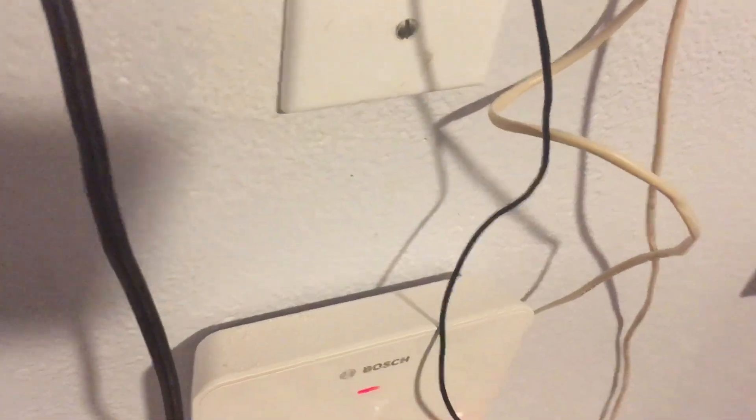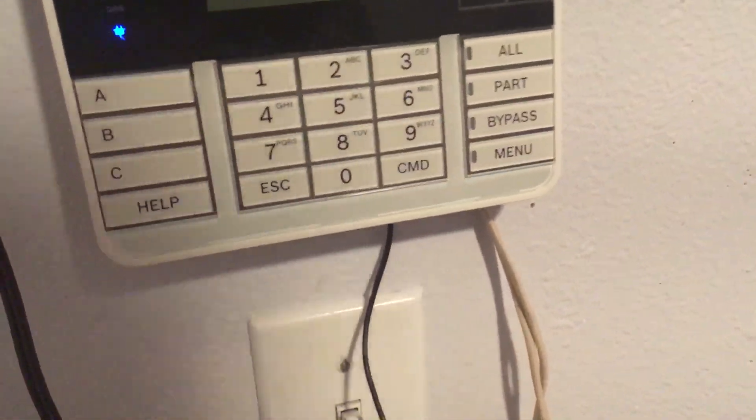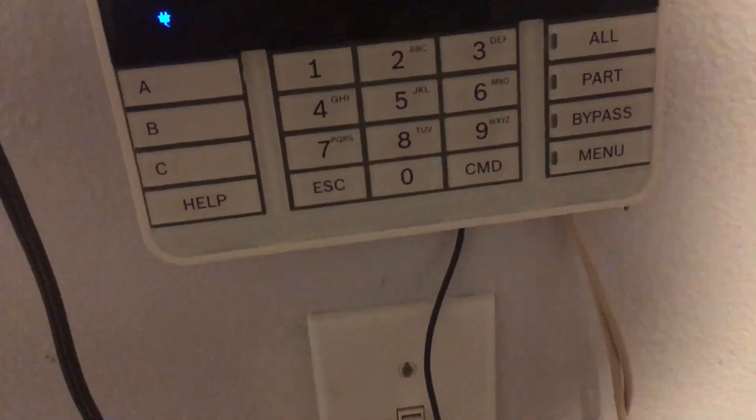If you want, the key fobs can be supervised. So if the key fob is not in range of the B-810 receiver within a certain amount of time, it will cause a trouble on the panel. I know DMP and Honeywell have these key fobs too and they can do similar things, but I thought I'd show the key fob on the B-series as one of Bosch's options.